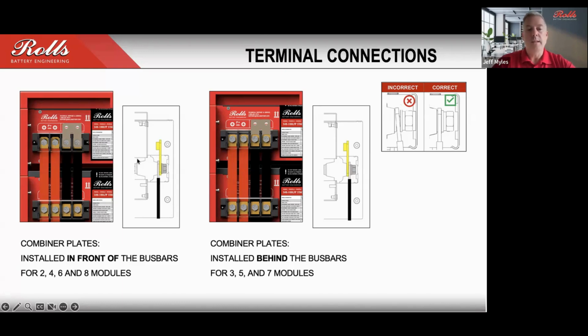You'll also, in the base and top assembly, get what we call a combiner plate. You can see on the top here on the negative connections, it's joining those dual bus bar connections, and then you would connect your negative lead to the inverter on that negative bus bar. When you're connecting the bus bars from unit to unit, it's important that you have them flush against the terminals.